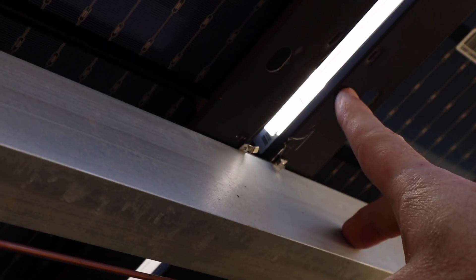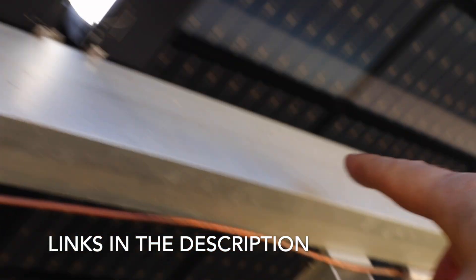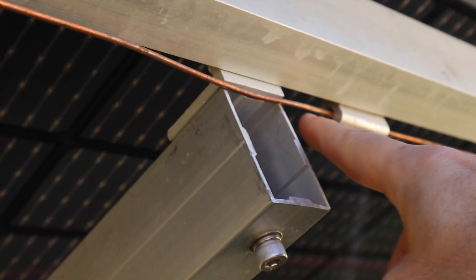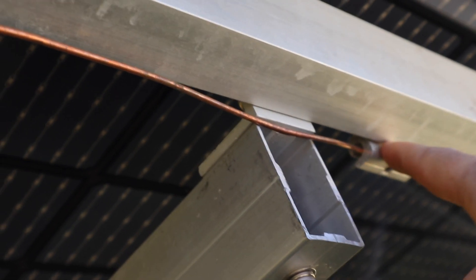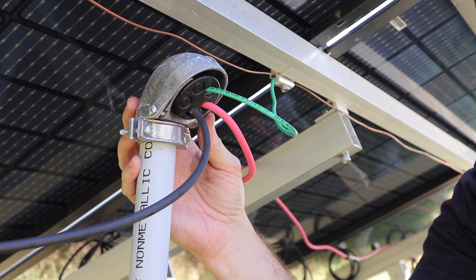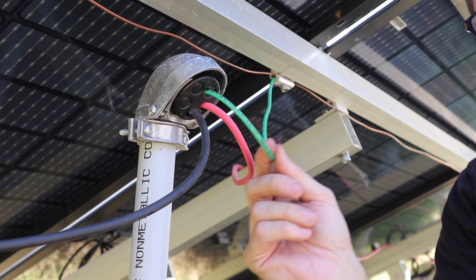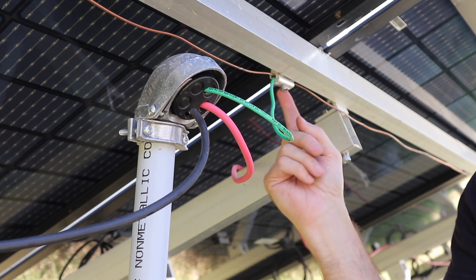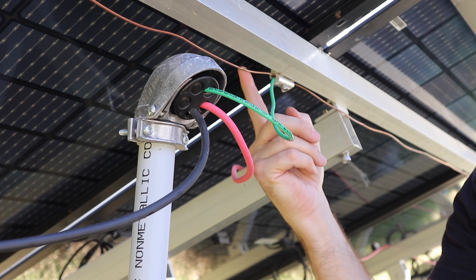First we have our Sirius solar panels bonded to our EG4 BrightMount with these clips. Additionally, we have these connectors which have our electrical grounding conductor — our bare copper wire — bonded with a clip on the back side. From our conduit that comes under the ground from the larger array, we've got our electrical grounding conductor coming up here and connecting with our clamp that has our bare copper wire in it.